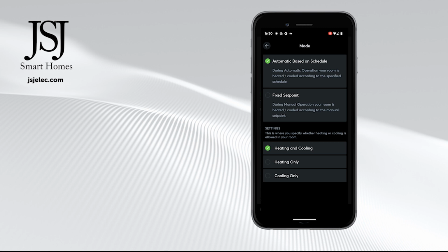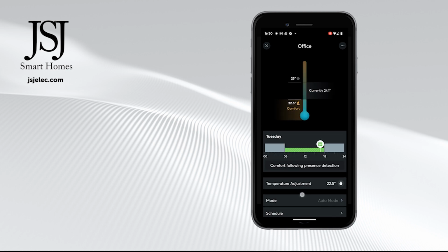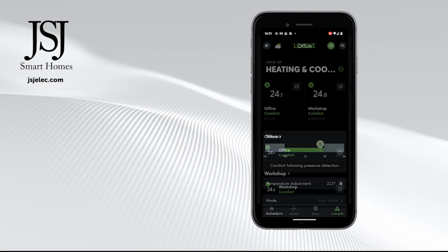If you like to be a little bit more specific, or you've got a particular purpose in mind for a room on a particular day, that you're going to be filling the room with flowers and you want to drop your temperature, not run the normal schedule, or you've got an old or a young person and you want to make sure that room stays at a nice high temperature, you can put a fixed set point on that temperature for that room and precisely tie it to that, and it will just deviate half a degree either way, but it will very accurately maintain that temperature throughout the period until you turn the fixed set point off. And that is everything to do with heating and cooling.